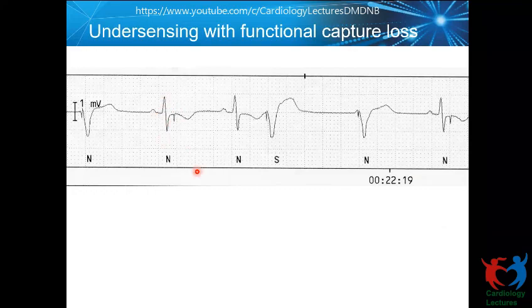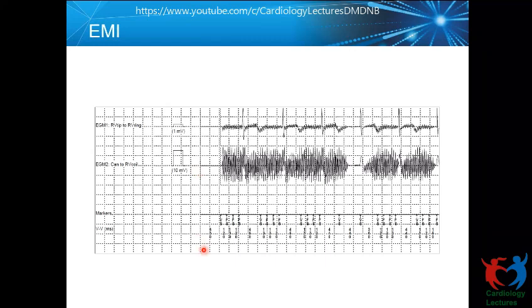And this is a typical example of electromagnetic interference. So here again, ICD. This is the near field electrogram, tip to ring electrogram. This is a tip to coil electrogram. It's like a far field, from the can to the RV coil. So this is like a unipolar electrogram, which is likely to pick up more electromagnetic interference. You can see that is reflecting in the near field as well. That is being oversensed by the device.